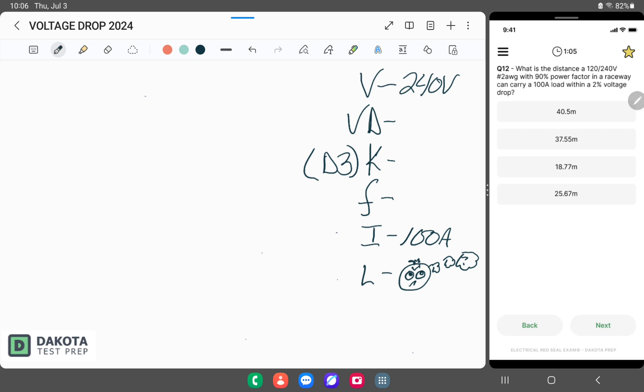Let's figure out our voltage drop. In this question, it specifically states 2%. So we're going to take our 240 applied voltage and multiply that by 2%, which gives us 4.8 volts. So 4.8 volts is the maximum amount of volts we can lose in this question.